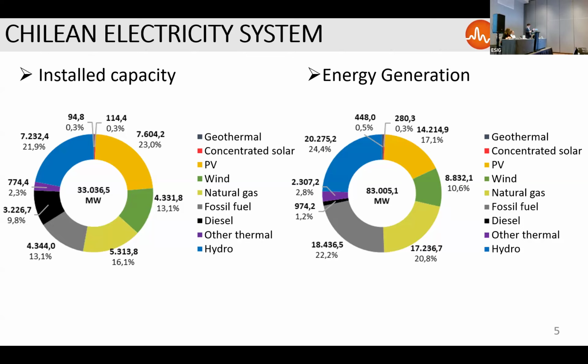On the left, you have the installed capacity. So you have roughly comparable sizes of PV generation, wind generation, gas, well, let's say thermal in general, gas or fossil fuels, and hydro. Then on the right, you have the actual generation, not the installed capacity, but the actual generation, and it somewhat corresponds to what you have on the left. Mostly all the installed generation units are working. You can probably see the only significant difference in the diesel generation. They're not used as much. Otherwise, it's kind of comparable.